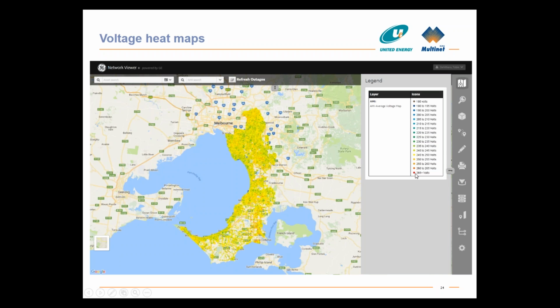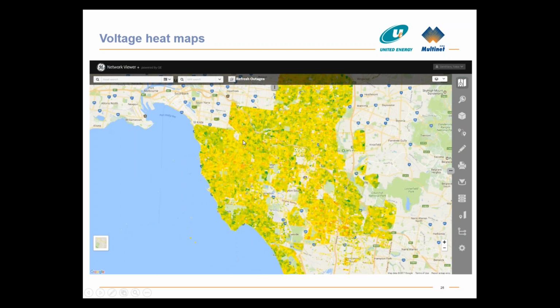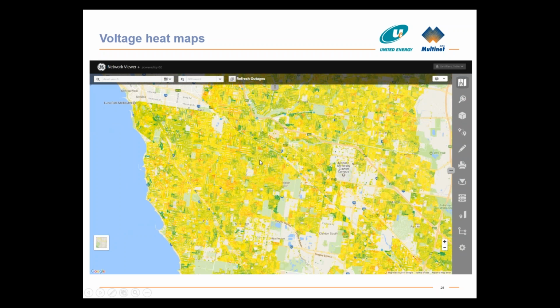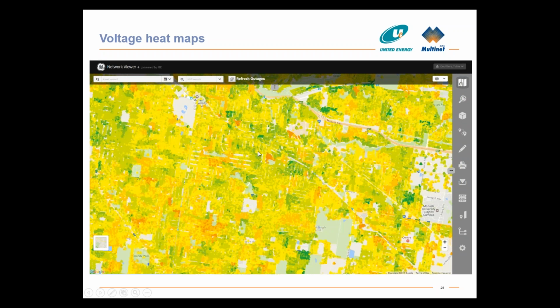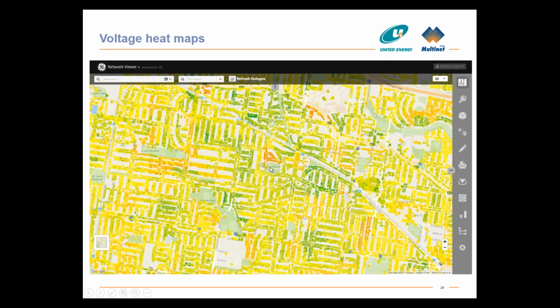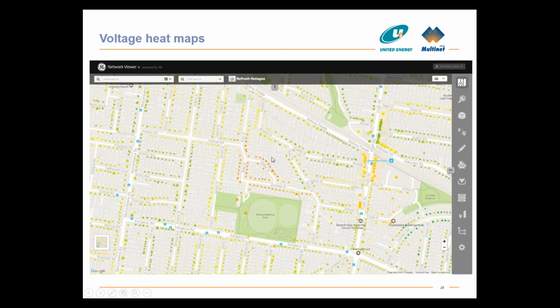And looking at the legend, you can see green everywhere. Where we've got a little bit of green, we've got probably close to undervolts, and everything where it starts to get to orange and red, we've got a bit of an overvolts issue. So we can go and zoom in on any area of the network and see, ooh, here's a few orange spots. We can zoom in a little bit closer on some of these orange ones. And as we zoom in, we can clearly see it's very specific clusters, which highlights that this is potentially a very specific substation that sits with the issue.